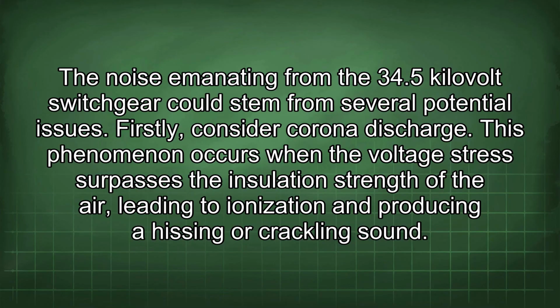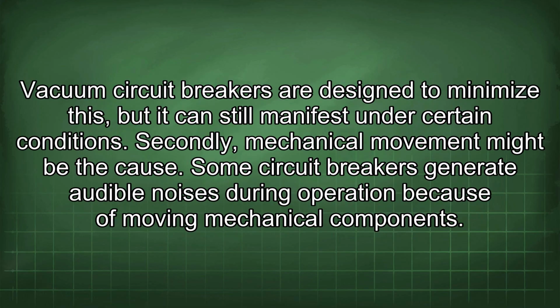The noise emanating from the 34.5 kV switchgear could stem from several potential issues. Firstly, consider corona discharge. This phenomenon occurs when the voltage stress surpasses the insulation strength of the air, leading to ionization and producing a hissing or crackling sound. Vacuum circuit breakers are designed to minimize this, but it can still manifest under certain conditions.